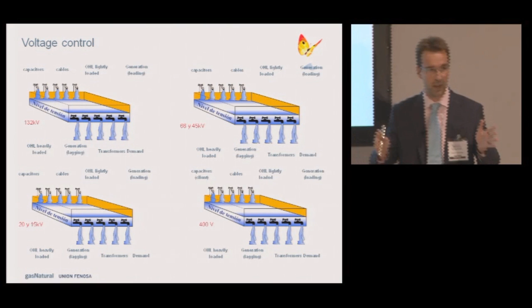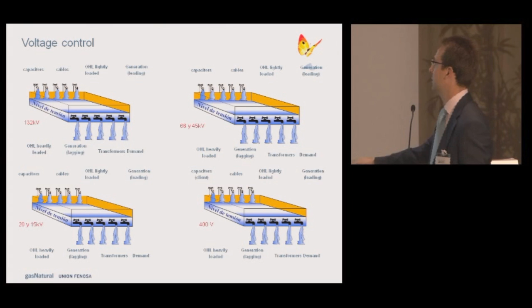When analyzing voltage control, remember the voltage control is the water tank. The water tank is different for every voltage level. The size of the tank and its taps are not the same for 132 kV, medium voltage -that's what we're talking about today- and low voltage.